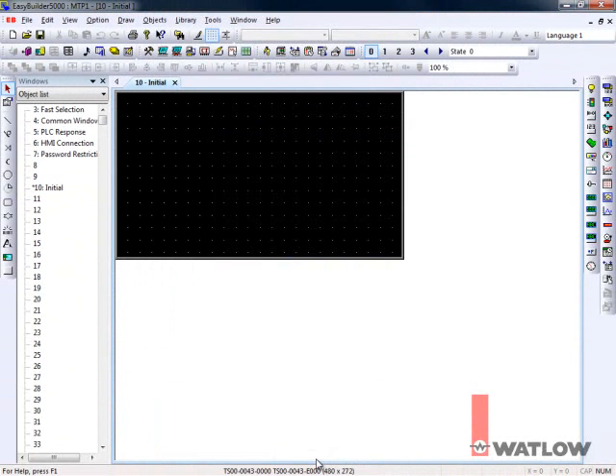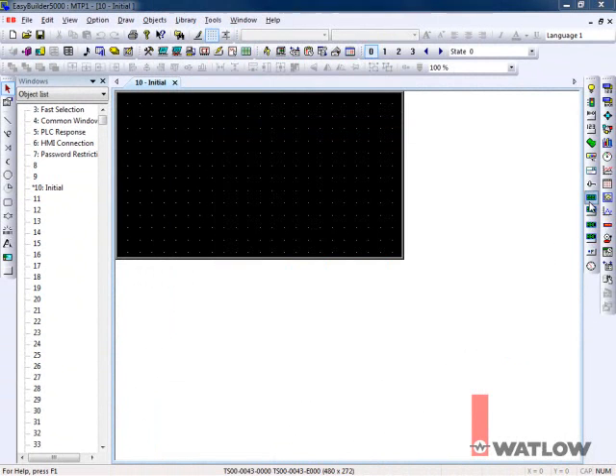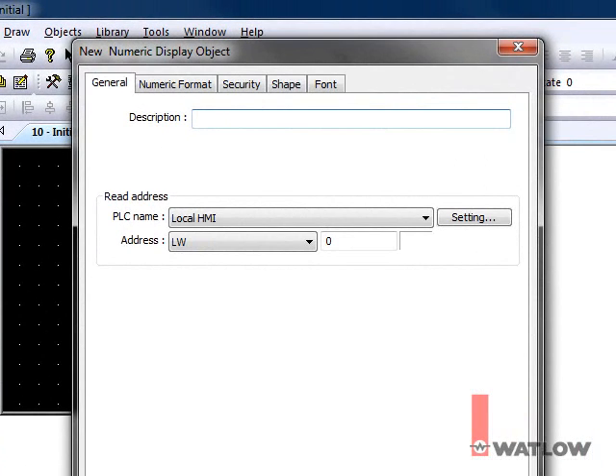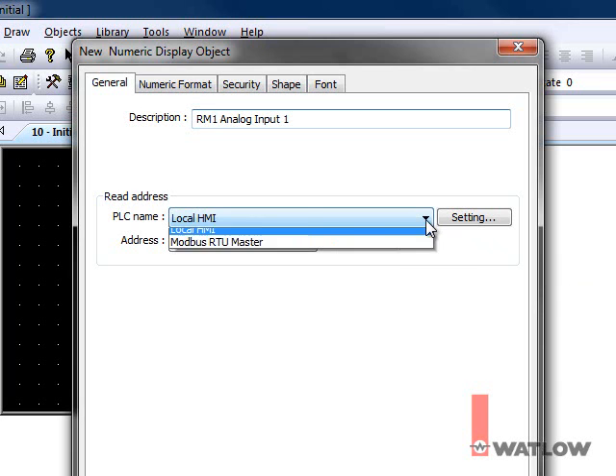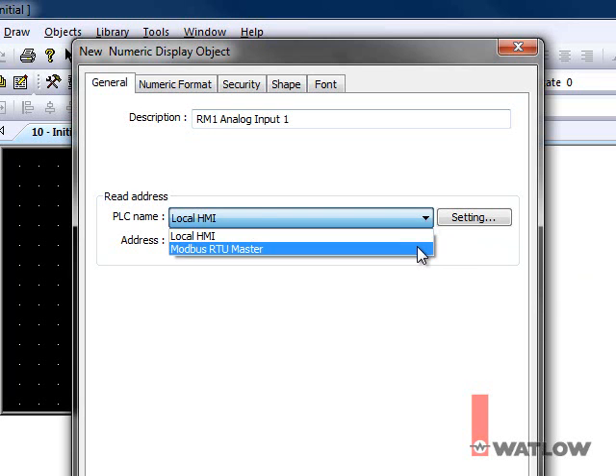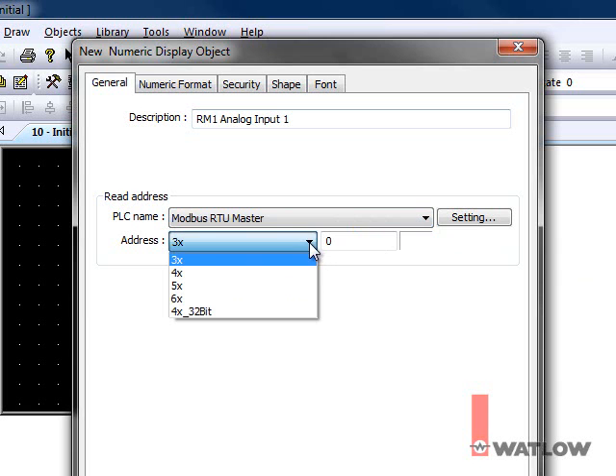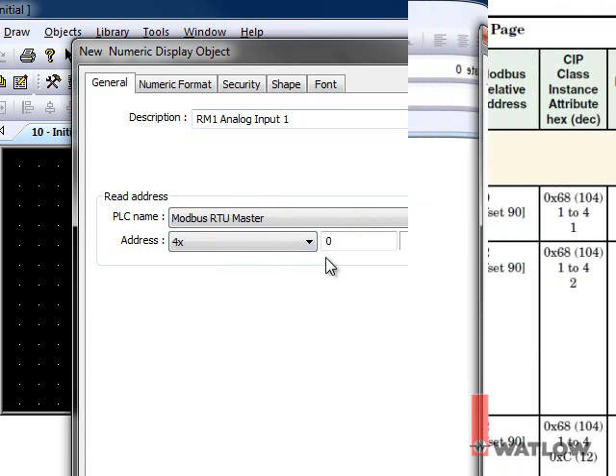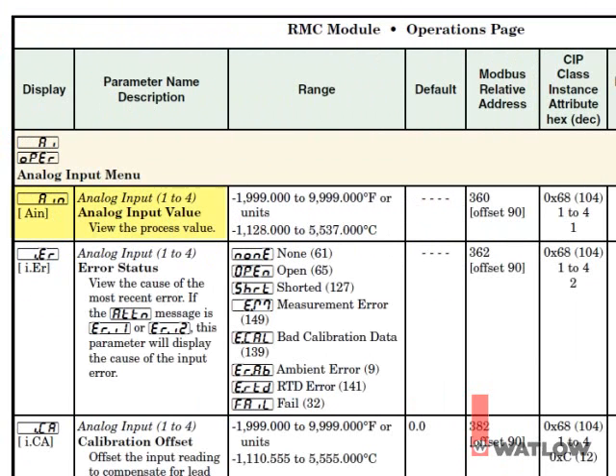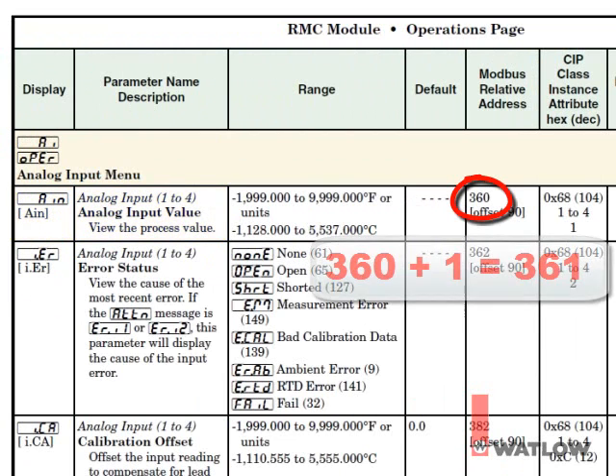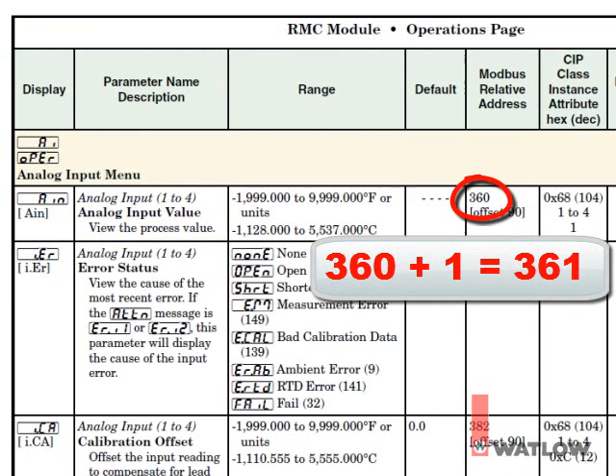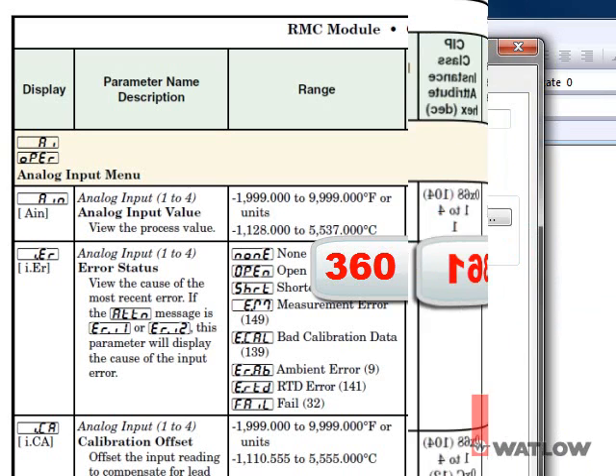Now we can start creating an interface. Let's use Numeric Displays to show the first two analog input values for each of the two RM modules on the OIT. Click the Numeric Display tool. Enter a description. Let's make this display the value of the first analog input in the RM at address 1. For PLC name, choose Modbus RTU Master. For address, choose 4X. Consulting the manual, you can find the address for the analog input 1's value is 360. You must add a 1 to the address indicated in the EZ-ZONE manuals, so enter 361.